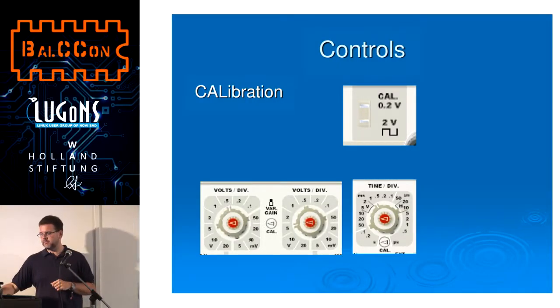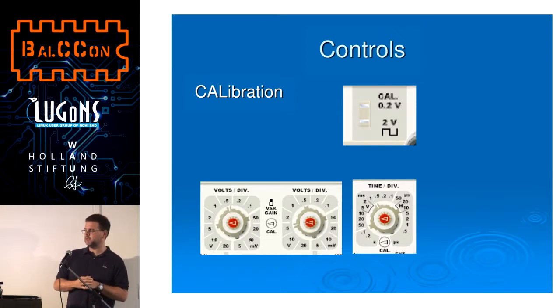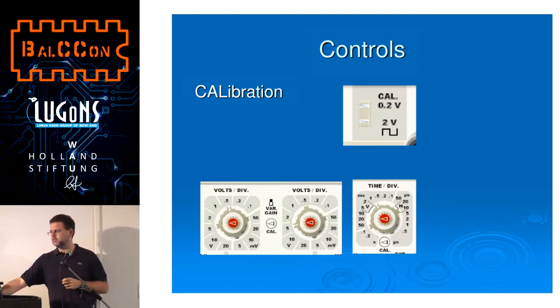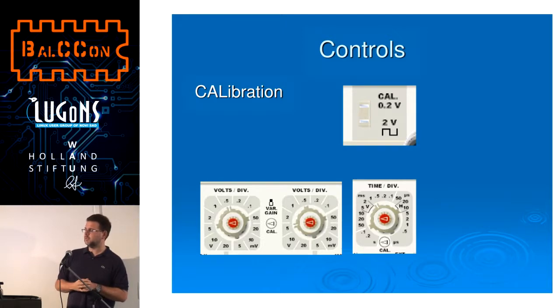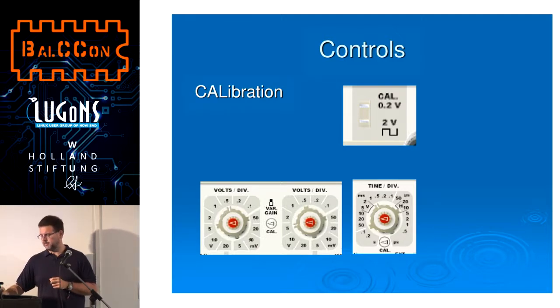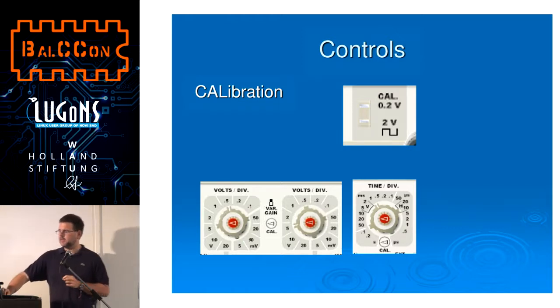Calibration: if you have played with the red potentiometers, you may have uncalibrated the oscilloscope. To calibrate it again, you connect your probe to a 0.5, 0.2, or 2 volt square wave and you can then scale it back to calibration. You know that this output is 2 volts square, and you set your controls so it represents just that wave.